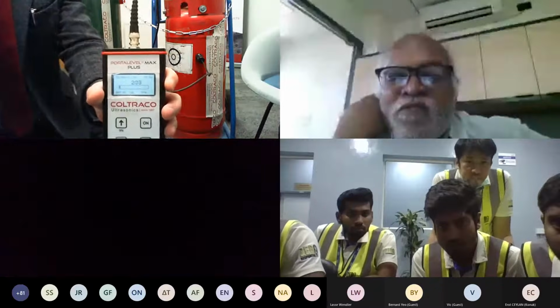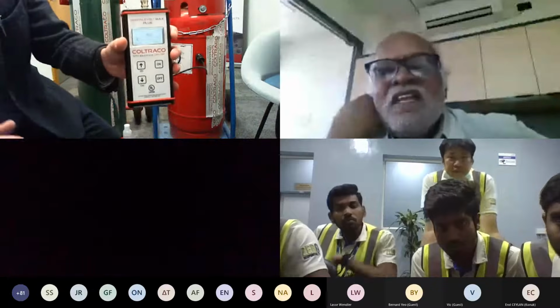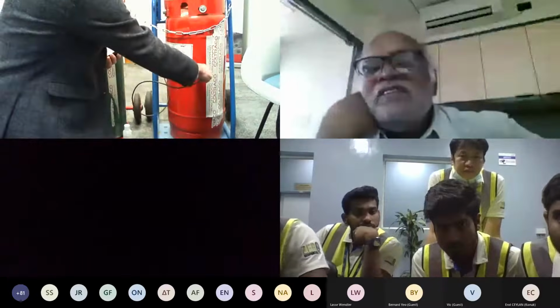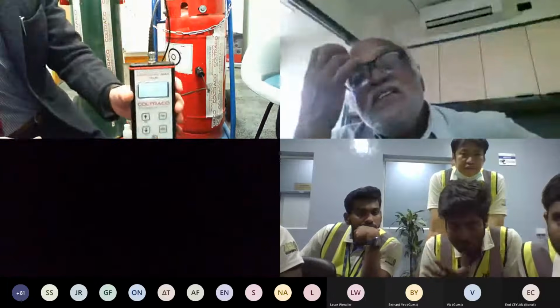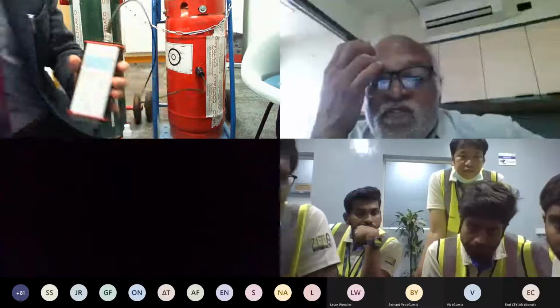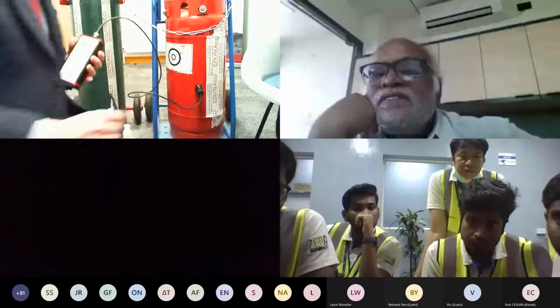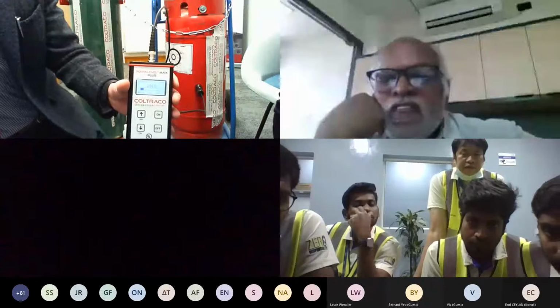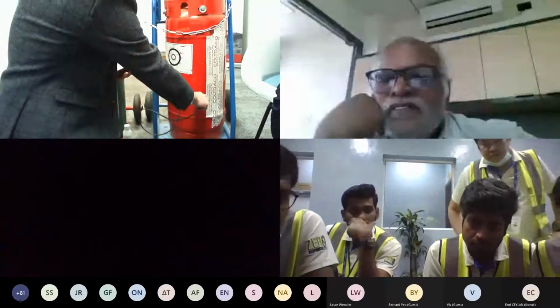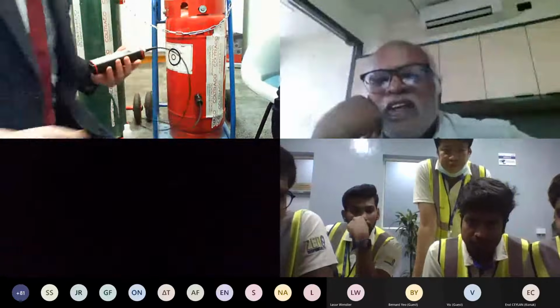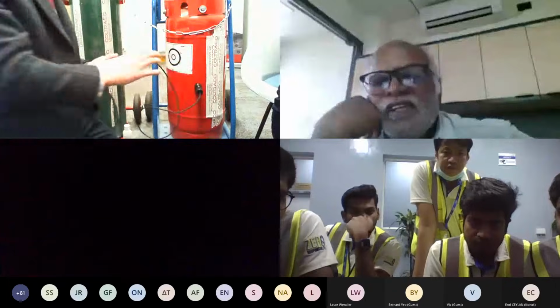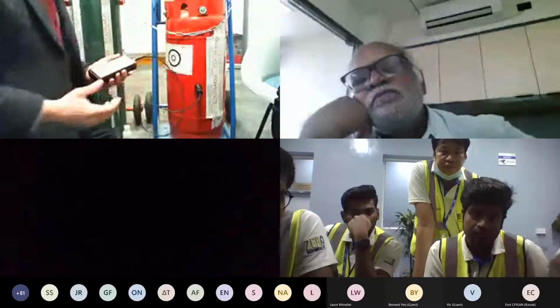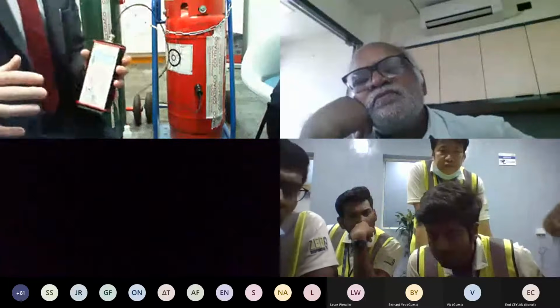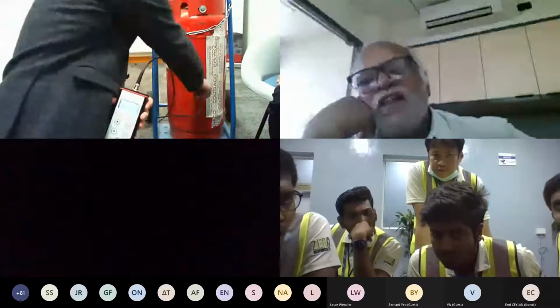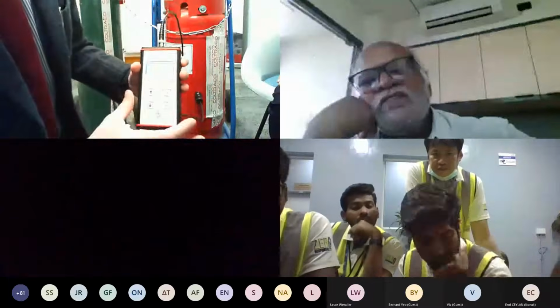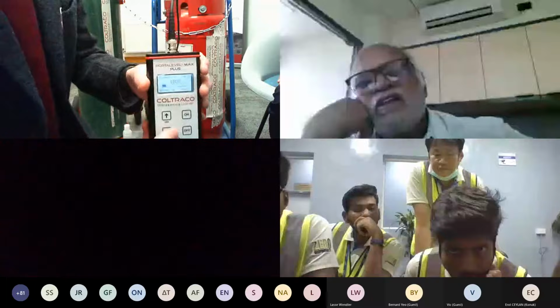See readings of around 200, 400, fluctuating between 350 and 450. Down again, and I'm getting similar readings through 250, 350, still quite low. Now I move down again, and I'm getting 1,900s, 2,000. And again, about 1,900s, 2,000s. So in this case, the higher readings are in the lower part of the cylinder. We always calibrate where we find the highest readings on the cylinder. So I place the sensor in the region of where I get high readings and press Cal again.